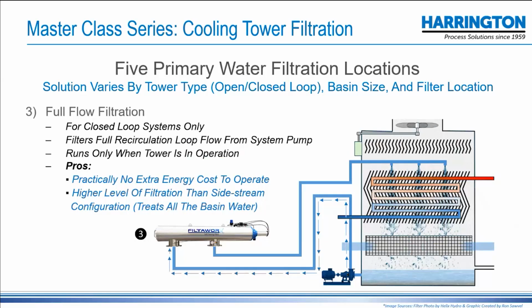And then another option is full flow filtration, where the entire flow is filtered coming out of the pump from the basin and going down through the spray nozzles into the dispersing elements and back to the basin. Good, but not best. You are ensuring that there will be no solids or buildup to speak of in the nozzles and dispersal elements, but the basin is still open to that inrush air of dust and debris coming in with the air, and it's going to fall right back down into the basin. It's not cleaning the basin. So again, the full recirculation loop into the basin is the very best option.